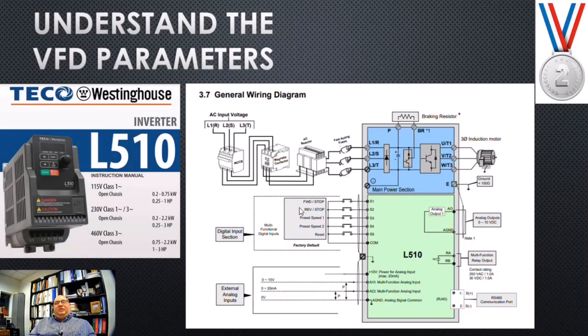So let's understand the VFD parameters. You have either an installation manual or a startup manual. Each one has its own set of information in there. Typically, the instruction manual will give you what you need to do a quicker type of startup, whereas the other manual will go into more depth in the menu system. But based on this particular diagram, let's take a look at it. This is L1, L2. The L3 is not being used. We only have 2 wires going into our drive, which would be a 115 drive, but notice how they use the same type of diagram with different notations on it.